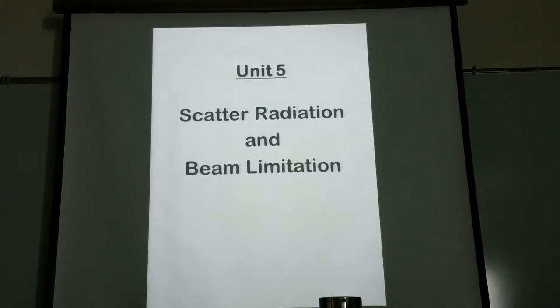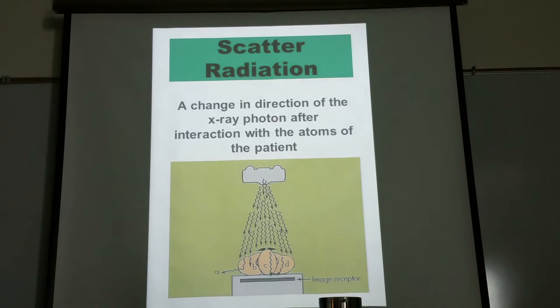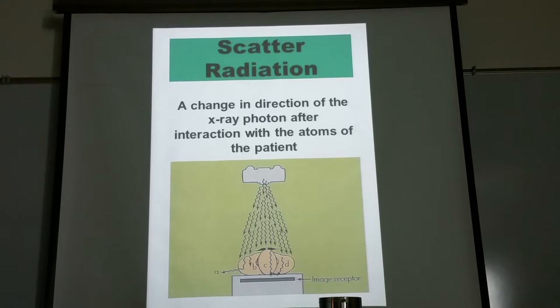If we can limit — control — the size of the x-ray beam, not only can we control the size of the primary beam, but also what's produced once it interacts with the patient. The primary beam interacts with the patient, and what's left is your remnant radiation. That includes both primary radiation and scatter radiation. So if I can control the size of my x-ray beam, I'm also controlling the size of the scatter radiation being produced.